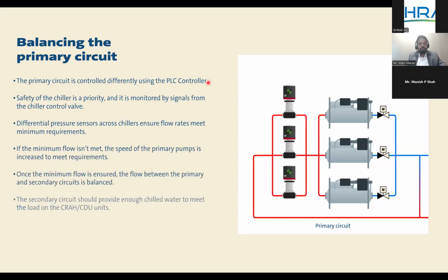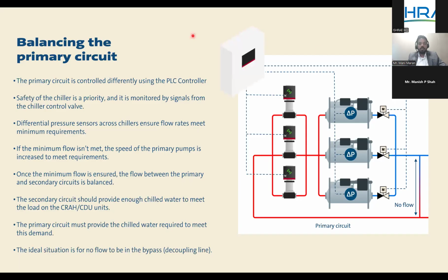And if the minimum flow is met, then based on the control logic which determines what the load on the secondary side is, the primary pump flow keeps varying. It increases or decreases based on the load changing on the secondary side, which is captured with the help of temperature sensors across the decoupler, which we will see in the next slide. So pretty simple, the DP sensor, the differential pressure sensor, or the flow sensor, feedback is given back to the controller to ensure the minimum flow, and that's how we protect the minimum flow. And based on the temperature difference across the decoupler, which varies based on the secondary side, the primary pump flow is modulated by increasing or decreasing its speed.